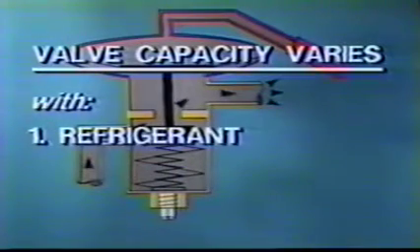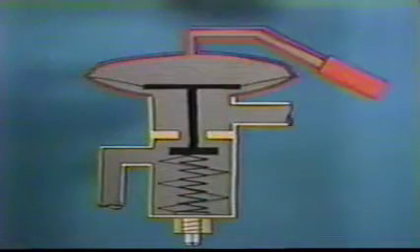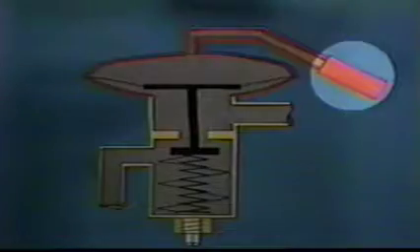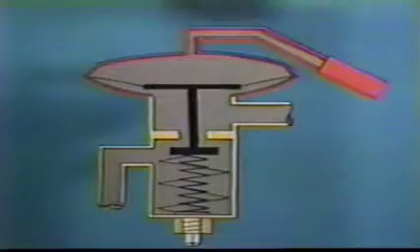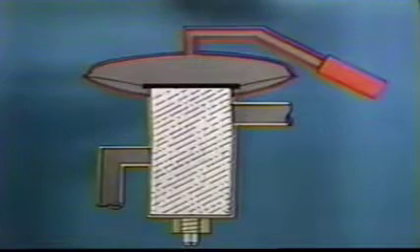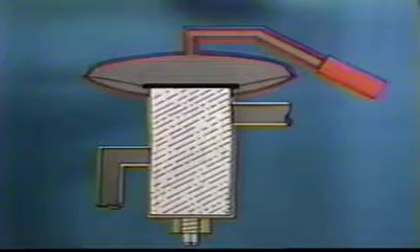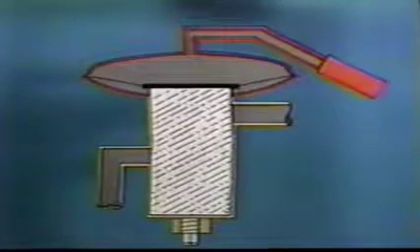Simply stated, the valve itself does not care what refrigerant type is being used in the system. While in practice, the valve's power element will be matched to a particular refrigerant type, the valve's purpose is to meter liquid refrigerant regardless of type.